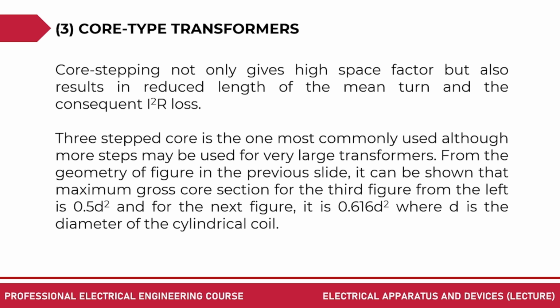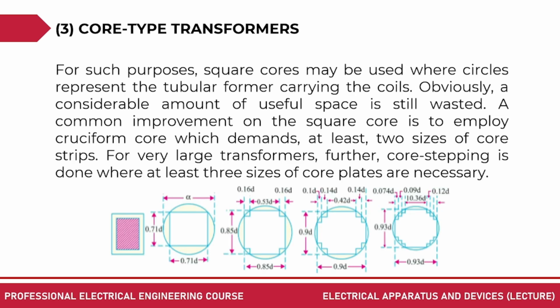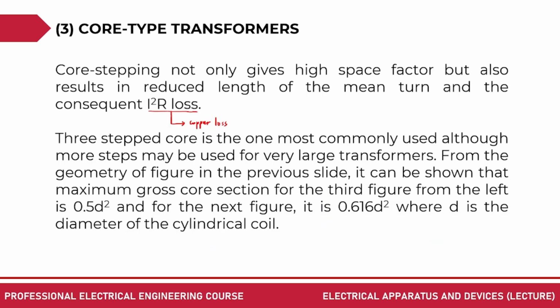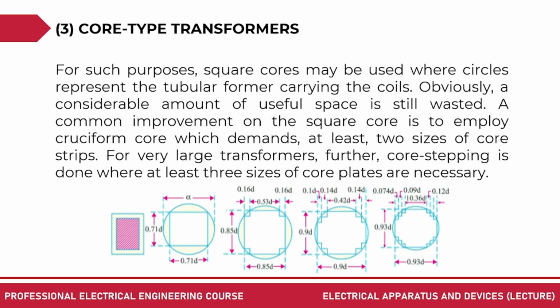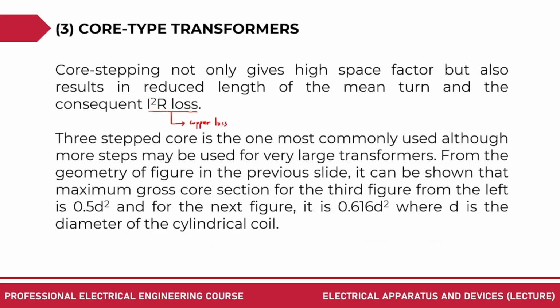So remember that when currents are flowing through the coil, and of course your coil has a resistive component, there is this copper loss, I squared R loss, or what we call the copper loss. Three-step core is one of the most commonly used, although more steps may be used for very large transformers. From the geometry of the figure in the previous slide, it can be shown that the maximum gross core section for the third figure from the left is 0.5 d squared. This is what we're talking about, that one. And for the next figure, it is 0.616 d squared, where d is the diameter of the cylindrical coil.